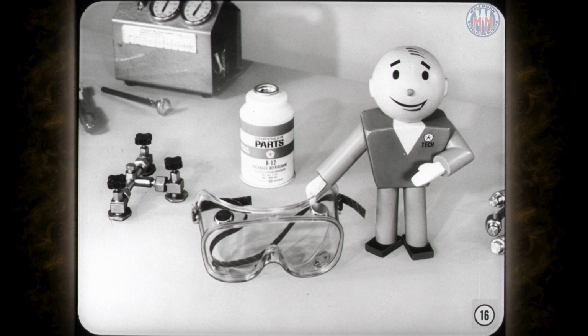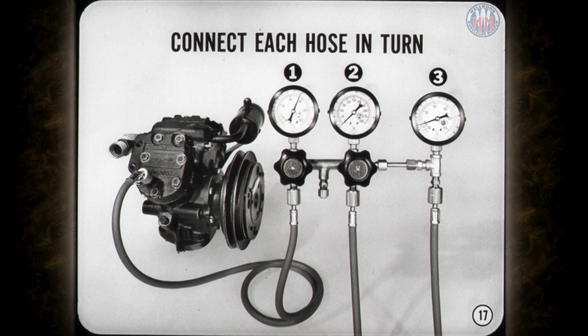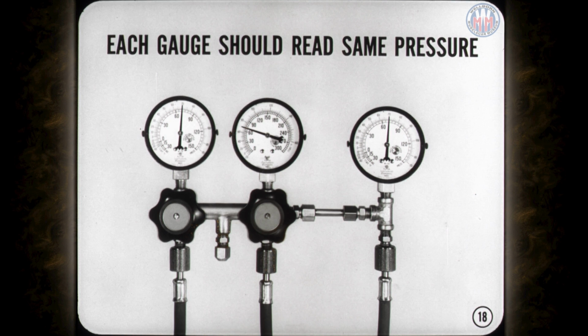Now, what's the word on gauge checking, Fred? Well, before I connect the hoses, I check the gauges by comparing their indications. All you do is connect each gauge hose in turn to the same service port at the compressor and note the gauge readings. Of course, the system must be shut down long enough for the pressure to stabilize. Each gauge should indicate the same pressure. If one gauge is off slightly, you can adjust it to agree with the other 2. But when you get a wide variation in the readings, the gauges probably need a calibration check.